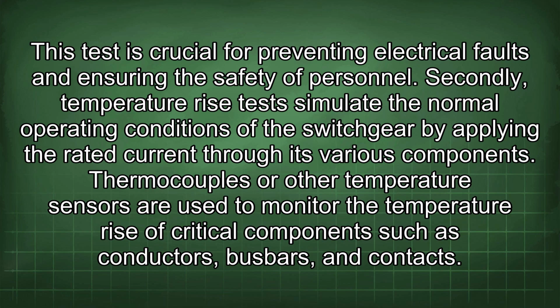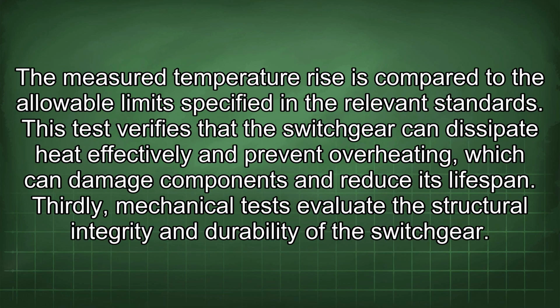Secondly, temperature rise tests simulate the normal operating conditions of the switchgear by applying the rated current through its various components. Thermocouples or other temperature sensors are used to monitor the temperature rise of critical components such as conductors, busbars, and contacts. The measured temperature rise is compared to the allowable limit specified in the relevant standards. This test verifies that the switchgear can dissipate heat effectively and prevent overheating, which can damage components and reduce its lifespan.